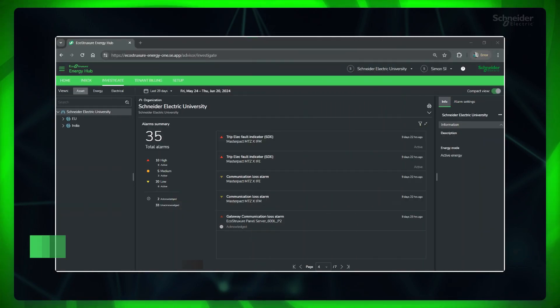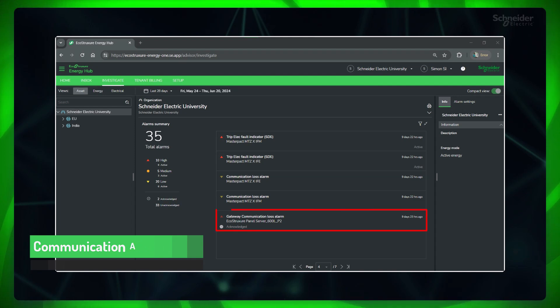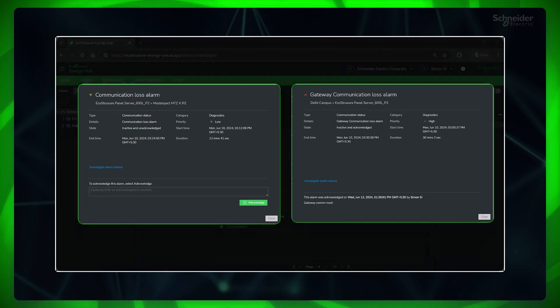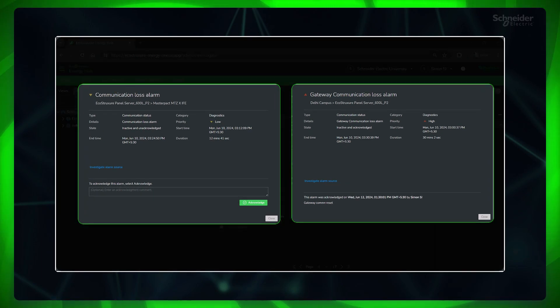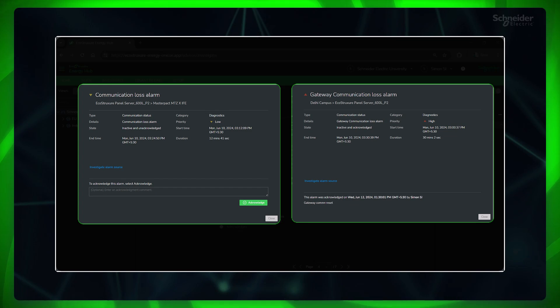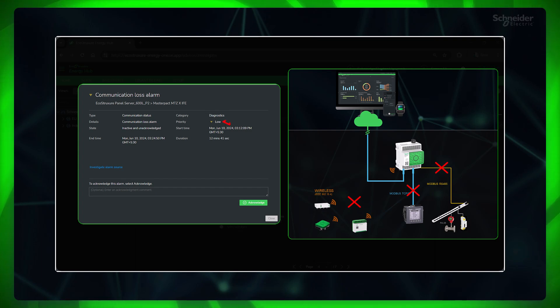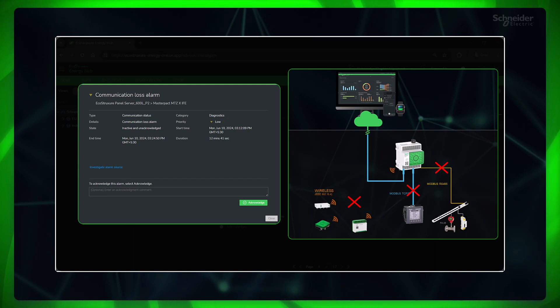In communication alarms, we have device communication loss and gateway communication loss alarms. These alarms do not require an active subscription and become available once the gateway is added to your site. They fall under the application category of diagnostics. When the communication between a device and the gateway is lost, a communication loss alarm is generated with low priority. The start time of this alarm is based on the device settings in the gateway, which is usually a few minutes.